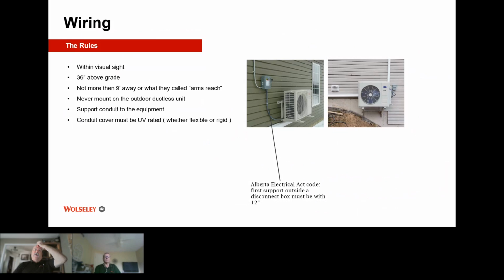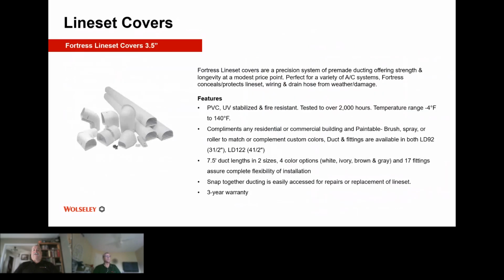They are looking for support for your electrical conduit from the disconnect to the unit, 12 inches below the conduit. And as I said, there are many options for line set covers out there. The two most common sizes are 3.5 inch and 4.5 inch. Just make sure you get the appropriate size. If you have more than one line set going in there, you might opt to go to the bigger size. The line set covers can come in some different colors. I am familiar with white, brown, or an ivory cream color. It just makes it look a lot better than seeing a whole bunch of spider webs of your Armaflex line set outside.